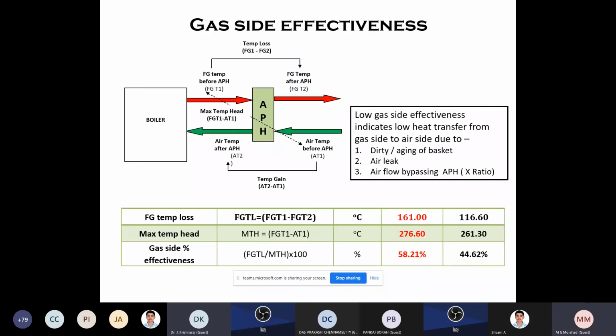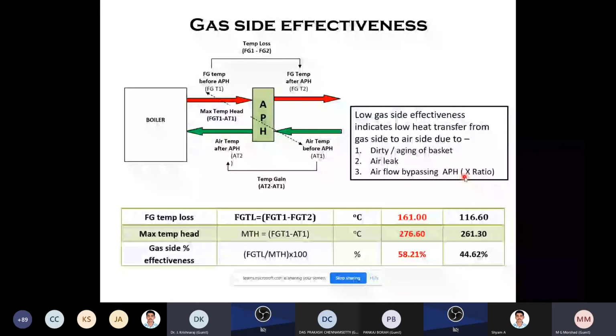Now how are we going to check the low performance of the air preheater, which can be due to various reasons? One is dirty or aging baskets. Then air leak, and air flow bypassing the air preheater. So these three reasons will degrade the performance of the air preheater. Suppose there is a clog in the baskets, the air will not pass and the heat exchange will not take place. If there is an air leak, it is a big body, a big size air preheater. So if the air sealing is not proper, what will happen? The air will leak from this side to this side, so automatically heating will not take place. And sometimes the air will not go here, it will bypass the air preheater and go. So these are the three things which decide the performance.